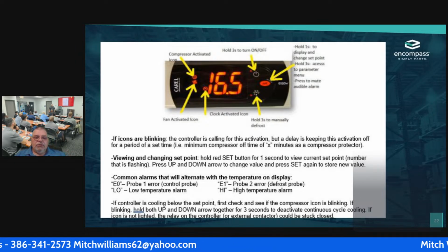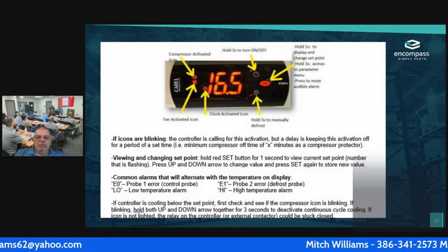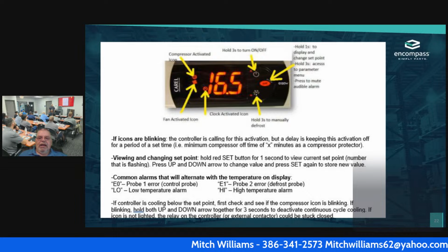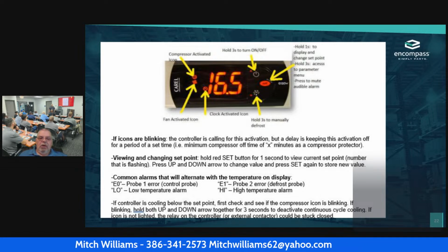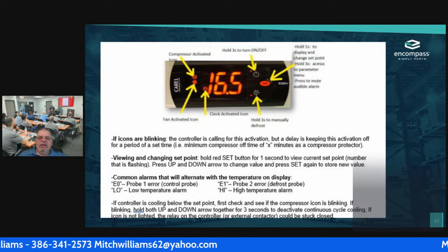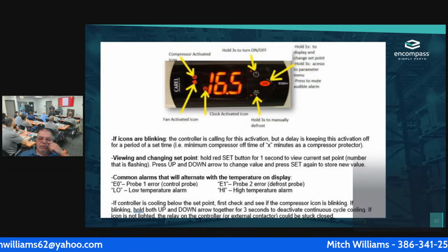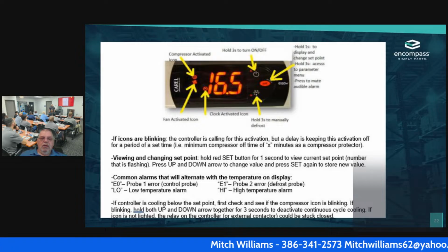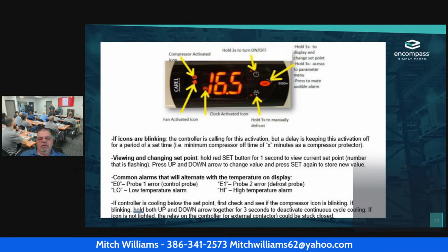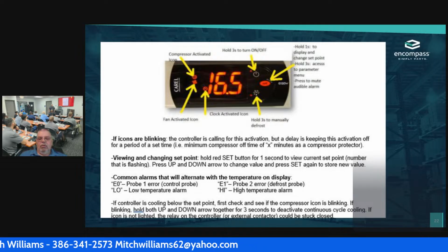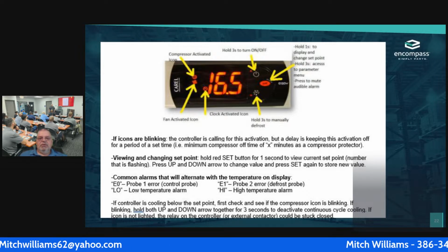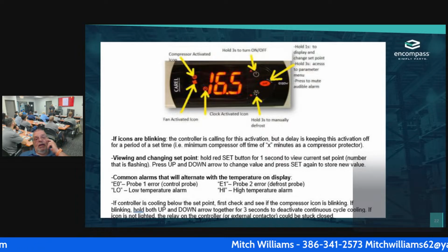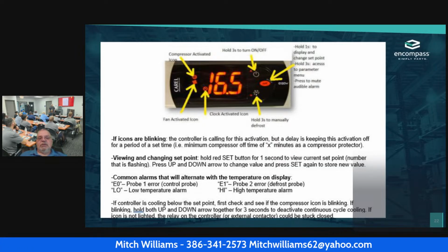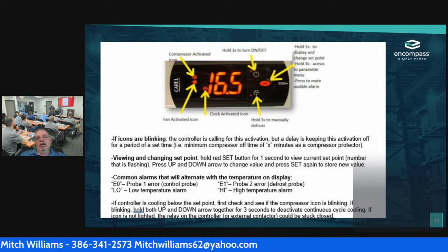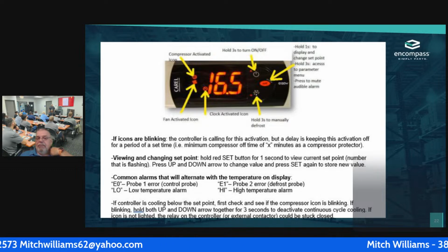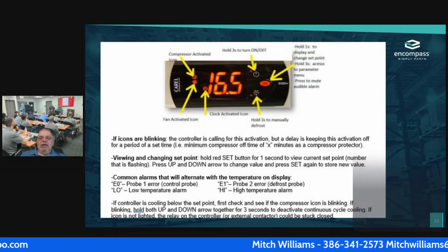Okay. If the controller is cooling below the set point, the first thing I'm going to do is check to see if the compressor icon is blinking. If it's blinking, hold both the up and the down arrow for 3 seconds. That deactivates the continuous cycle cooling. If that icon is not lit, then of course the relay to the control or the external contactor could be stuck closed. So I'll need to ohm that out and check that. Once again, the first thing I'm going to do, if I need to do that, before I pull my meter out, I'm going to make sure that I ohm everything out.